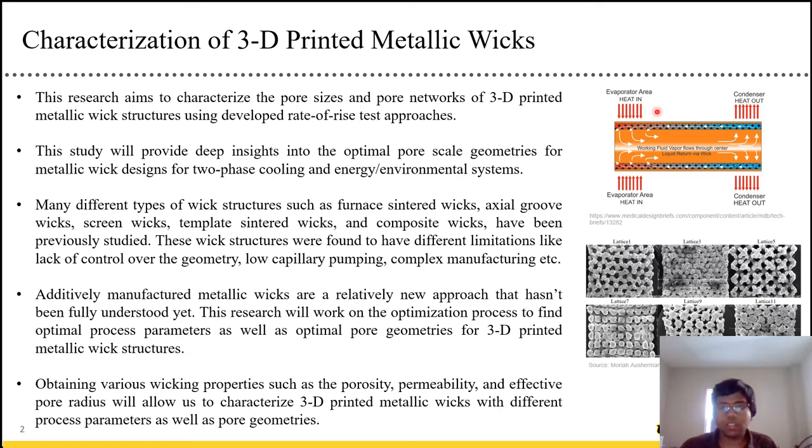As you can see on the top right image here, you have the wick structure and there's a fluid inside the wick structure. When it's in contact with the hot area, the fluid evaporates and expands over to the other side. And once it's on the cold region, it condenses and forms the fluid, and the wicking capability of the wick structure allows it to move from the cold area back to the hot area.